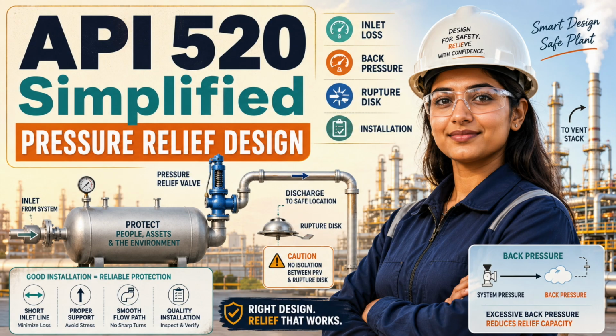Turbulence matters as well. A relief valve located immediately downstream of a control valve, pressure-reducing station, sharp elbow, T or high-velocity restriction may sense an unstable pressure field. Convenient layout is not always good hydraulic design. The outlet side can be just as decisive. Back pressure can determine valve type, available capacity, correction factors, and stability.